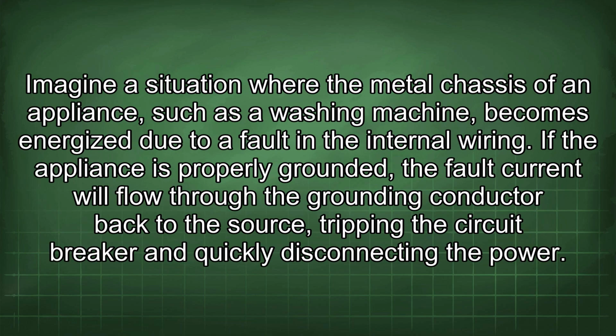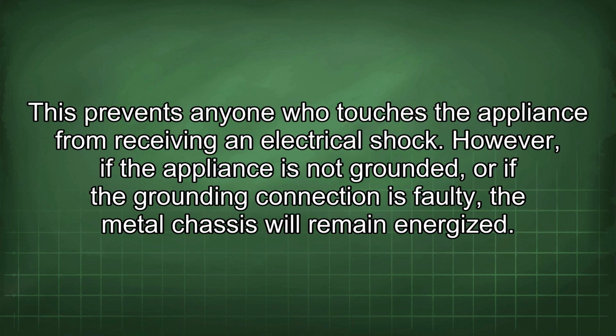Imagine a situation where the metal chassis of an appliance, such as a washing machine, becomes energized due to a fault in the internal wiring. If the appliance is properly grounded, the fault current will flow through the grounding conductor back to the source, tripping the circuit breaker and quickly disconnecting the power. This prevents anyone who touches the appliance from receiving an electrical shock.